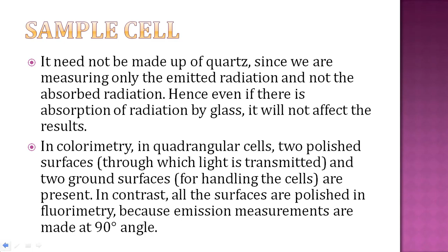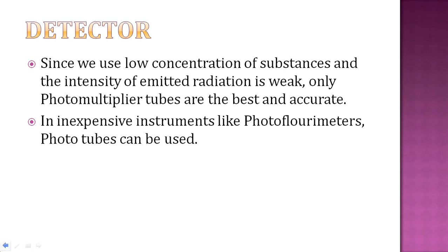Next is the detector. The emitted radiation is mostly visible radiation in case of fluorimetry and sometimes UV radiation. To measure the intensity of such radiations, photovoltaic cells, phototubes or photomultiplier tubes can be used. But we use low concentrations of substances and the emitted radiation is also very weak. So only photomultiplier tubes, meaning PMTs, are the best and most accurate. In inexpensive instruments like photofluorimeters, phototubes can also be used.